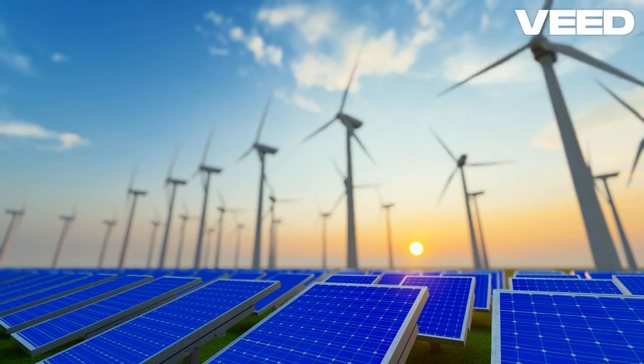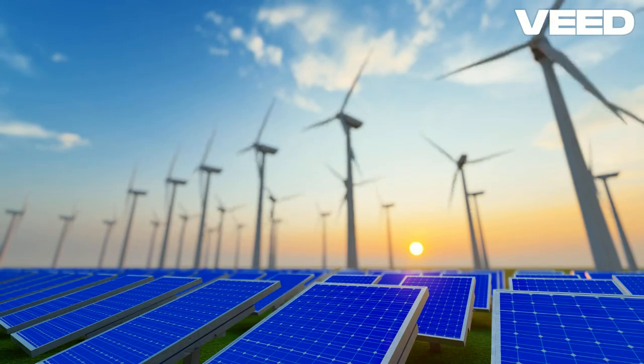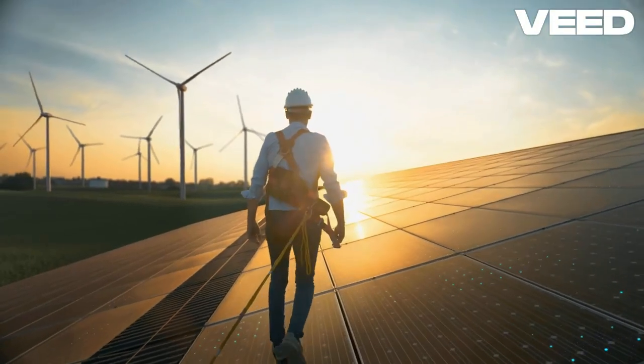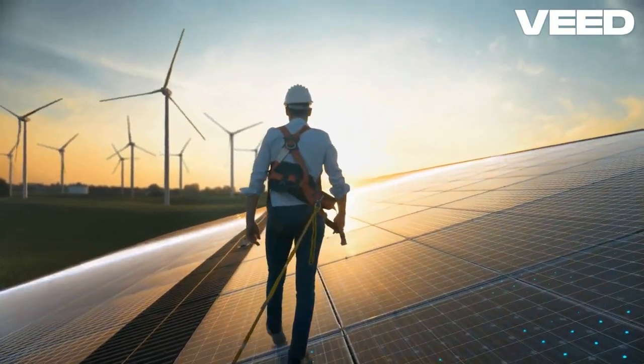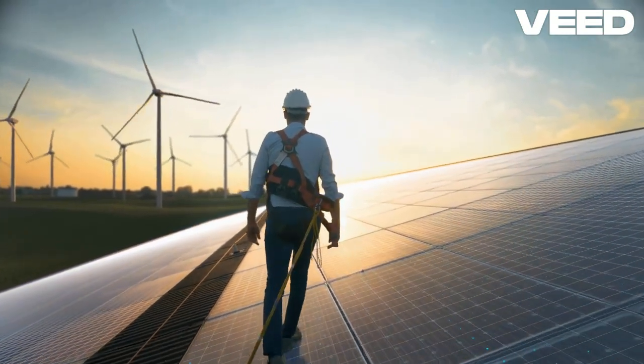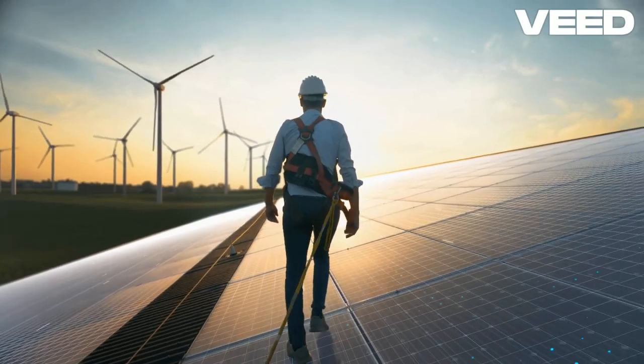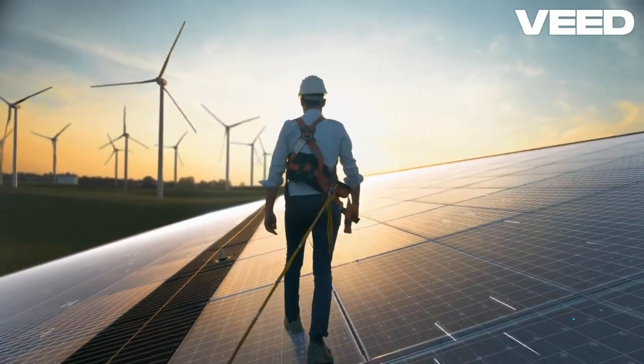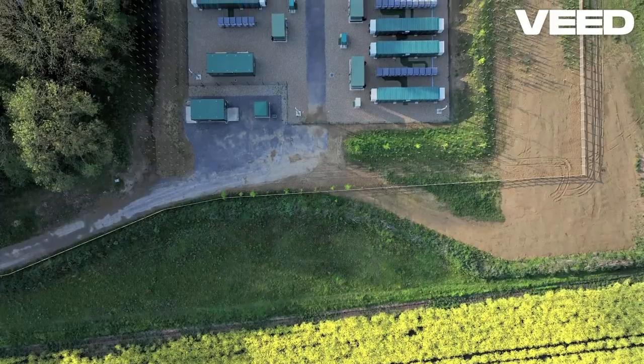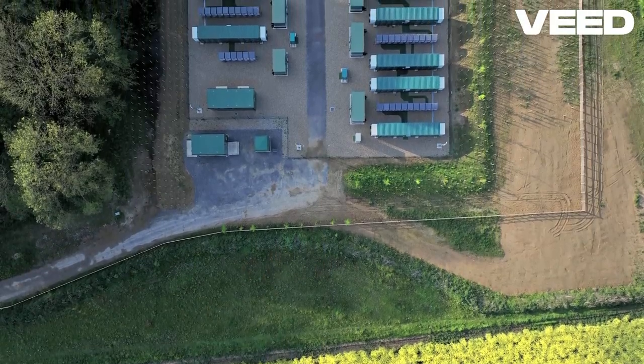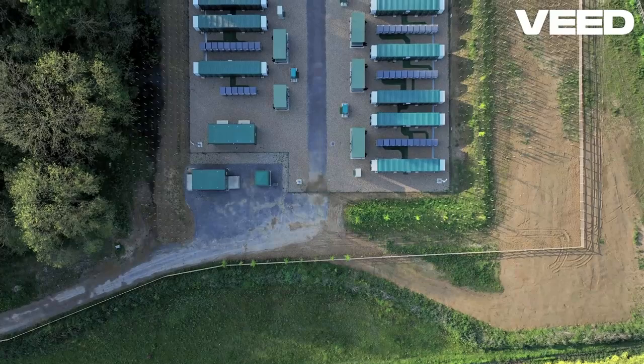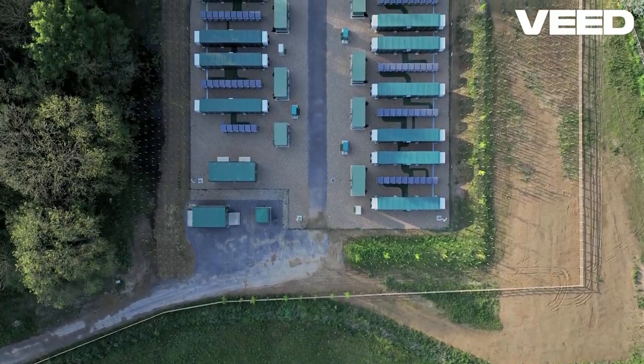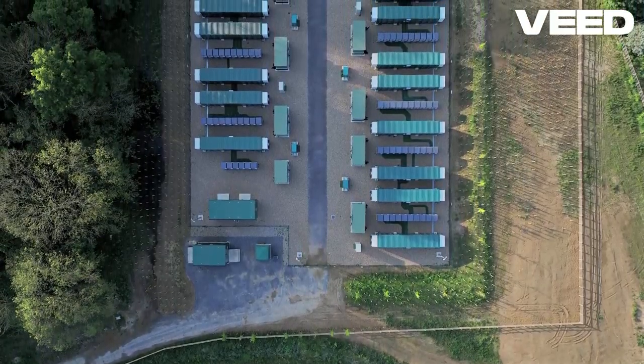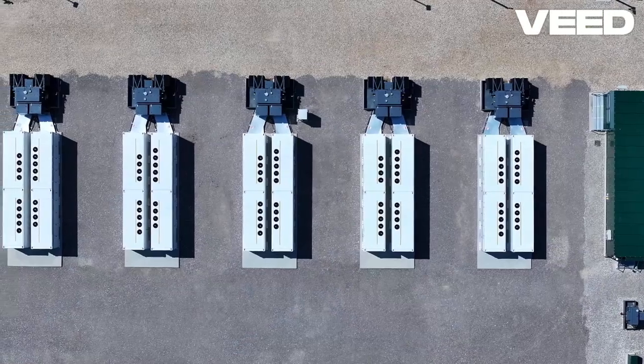Here's where advanced control strategies come into play. Grid-forming inverters are one of the cutting-edge solutions. They emulate the inertial response of traditional generators, stabilizing the grid even without rotating mass. Battery energy storage systems, BESS, also provide fast-acting frequency support. They can inject or absorb power in milliseconds, helping to smooth out rapid fluctuations.